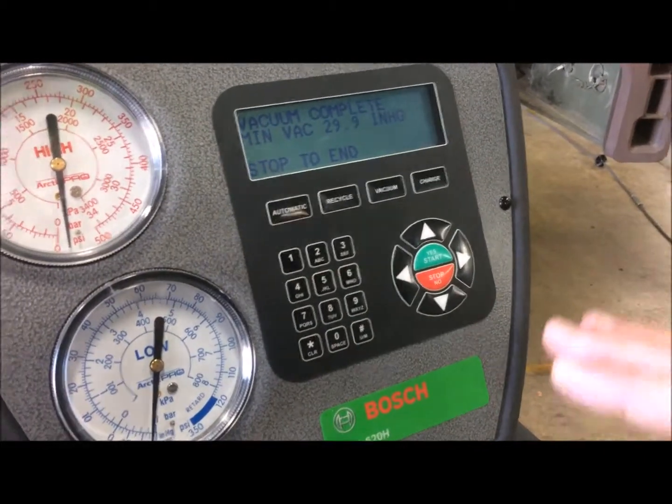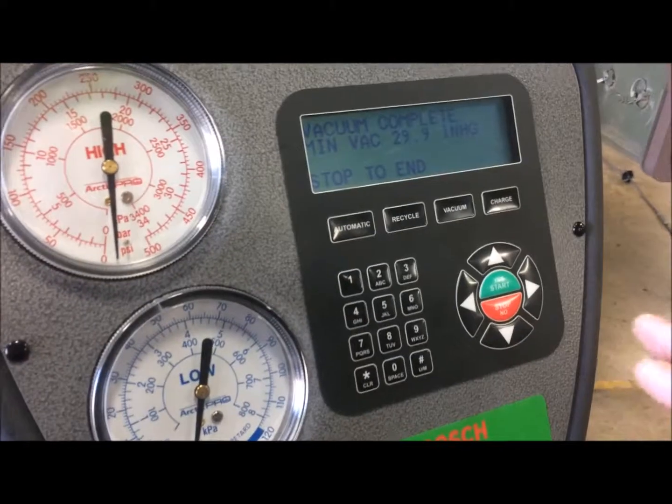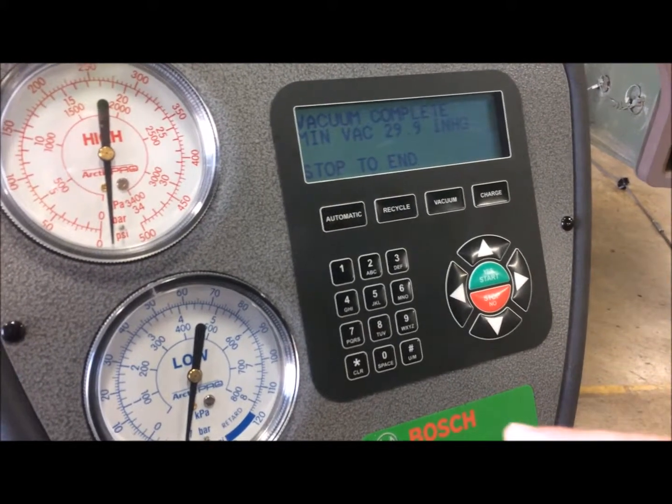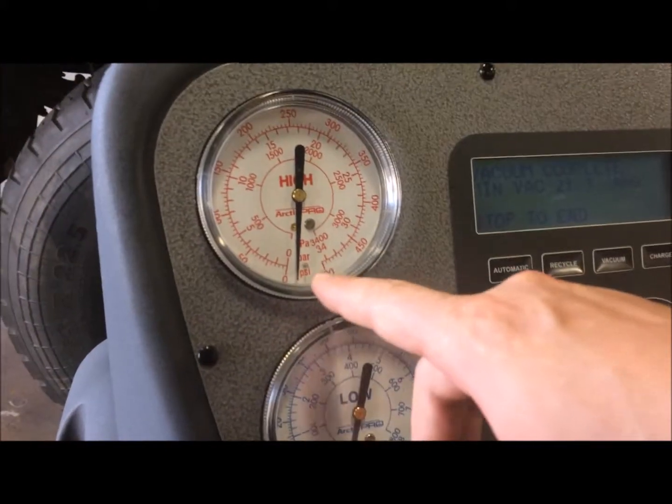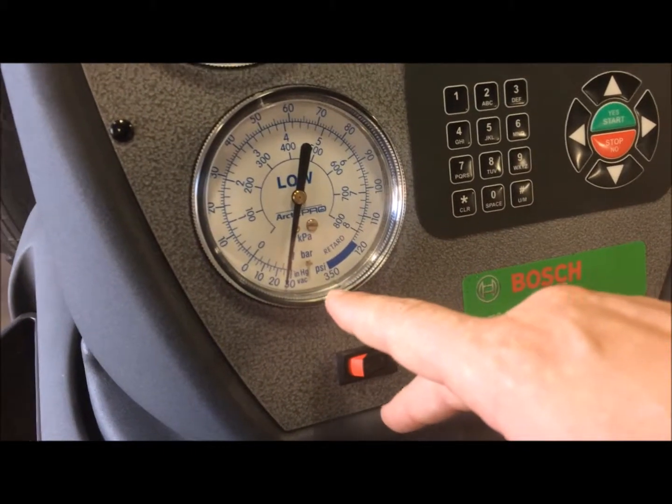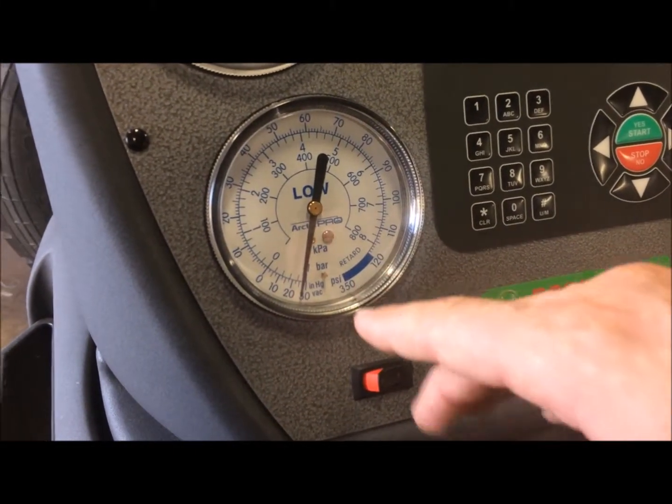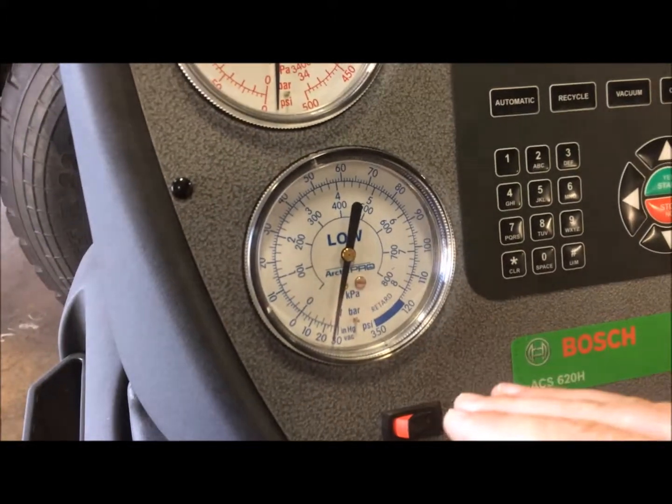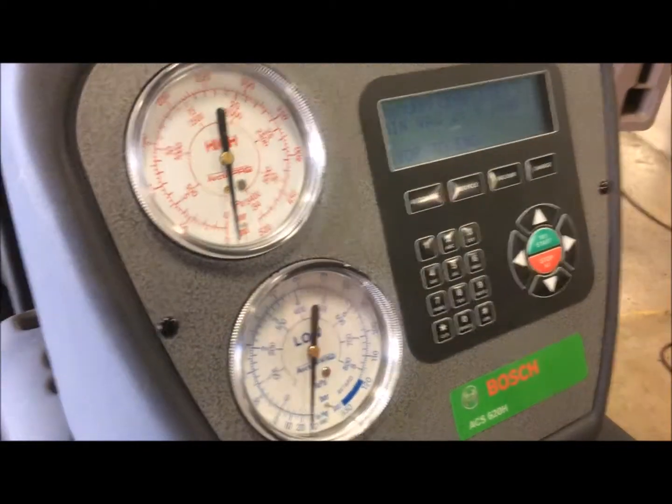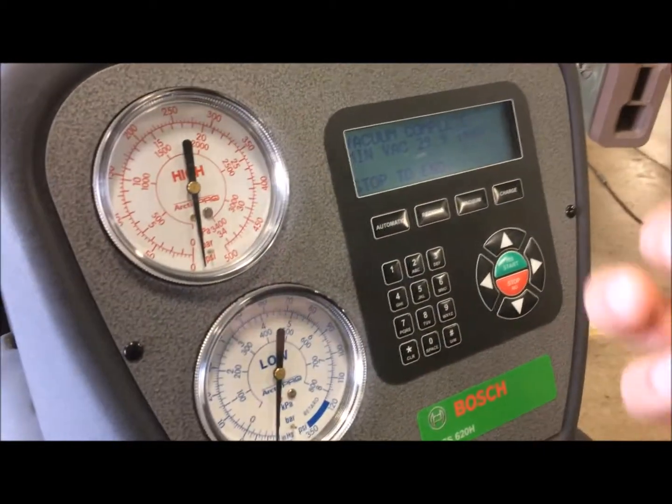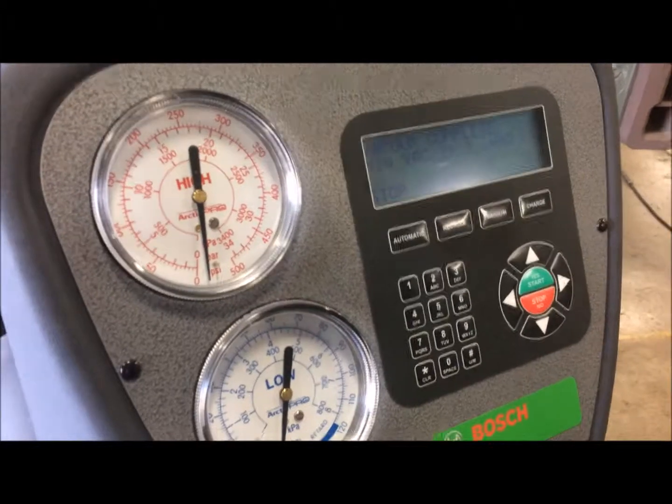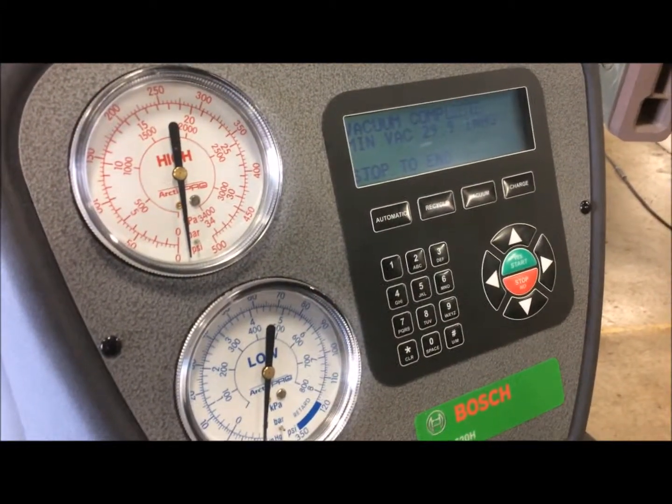Alright, now the vacuum test is complete. We let it sit for 5 minutes and check the pressure. So we're at 0 PSI and we're holding right about 27 inches of vacuum. It's really good. Now what that tells you is that the system is holding vacuum and you don't have any kind of leaks into the fittings or lines or any of the components, because what it would do is suck in air from the outside.